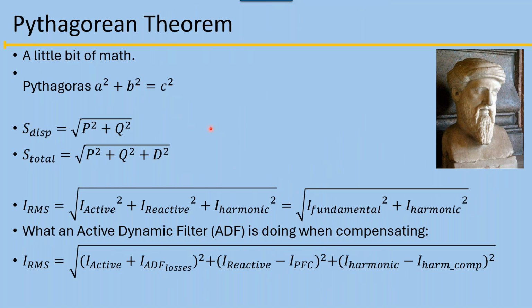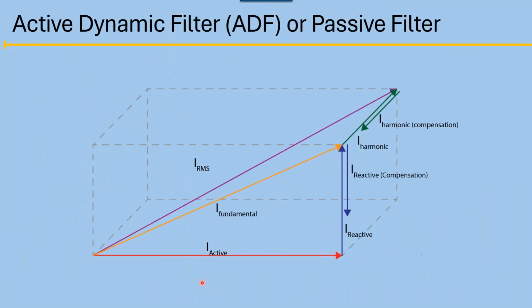Going back to Pythagorean's theorem, displacement is P plus Q, the total is P plus Q plus D, and D is distortion. When we get into active harmonic filters, they also call them dynamic filters. What we're doing is taking the active and subtracting and canceling out part of the reactance and the harmonics, getting rid of all that so you can improve it. That's how it's actually set up, and we'll talk more about that.